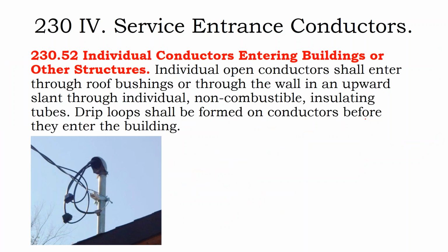So here we have a gooseneck entering the building, with requirements for that. We see this drip loop requirement. So you might say, well, that's a tangle of wires and it's a mess. Well, the reason is you have this overhead exposed wire. It's going to get rained on, and they want the rain to fall off the wire before it gets to this tap connection, and they don't want that water also going into the building.